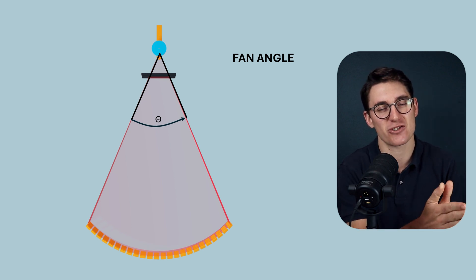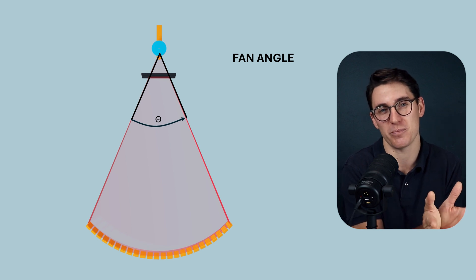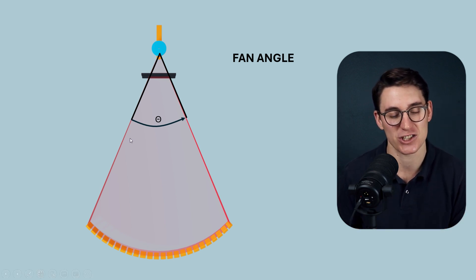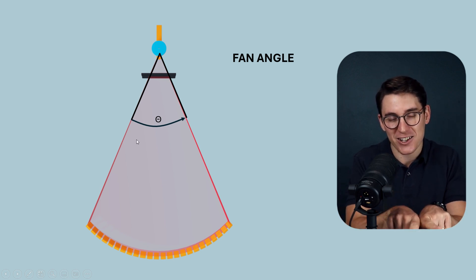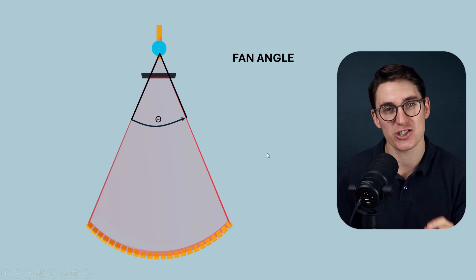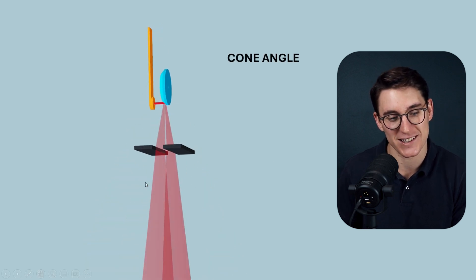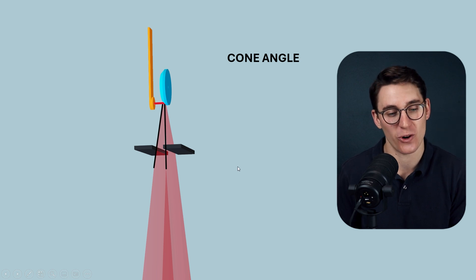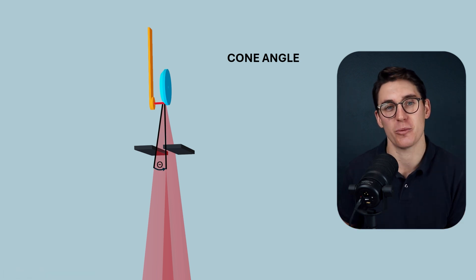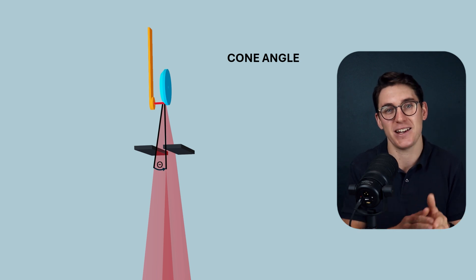When we look at third generation CT scanners, we describe that x-ray beam as being a fan beam — though technically that's not correct. A fan beam shouldn't have any width in the z-axis. The fan angle is the angle of the beam in the x-y plane, the axial plane cutting across the patient. In fact, third generation CT scanners do have some width in the z-axis, and this angle created is what's known as the cone angle. The third generation x-ray beam is technically a narrow cone beam, made narrow by collimators.